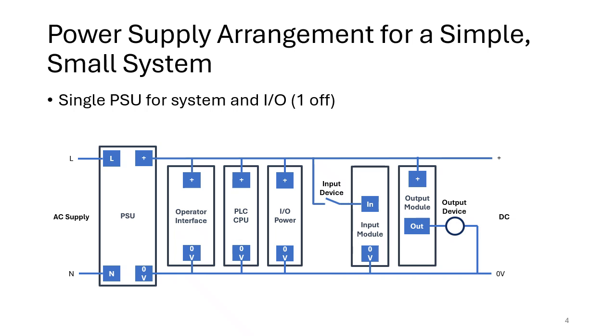This is fine where you have small currents. Typically, you might use maybe a 5 amp power supply or a 10 amp power supply, and that can be more than enough to power all of these components together. But as the systems get larger, you typically run out of power on the output side, but you may also run out of power on the input side and also for the other devices that you're trying to control.